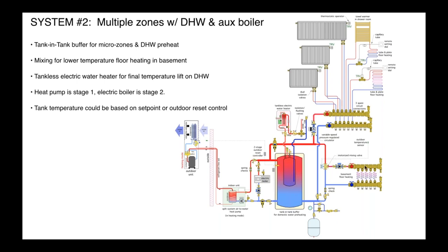And I purposely threw another one in. If we're doing slabs in the basement, we could do a little motorized mixing valve, and we could blend that water temperature down. You get these very well insulated houses. The loads on these basements are tiny. They might be 5,000 BTUs per hour at design. Water temperature requirements, 85 degree water at design. So we could mix it down for something like that, okay?